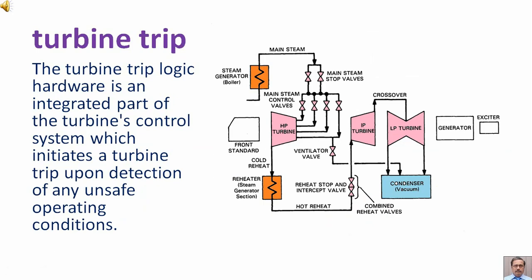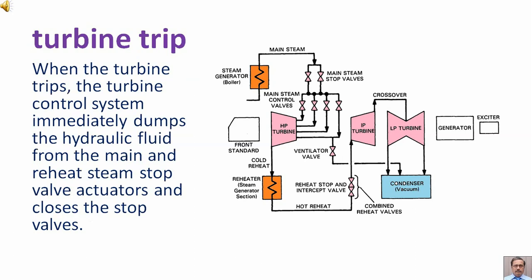Turbine trip. The turbine trip logic hardware is an integrated part of the turbine's control system, which initiates a turbine trip upon detection of any unsafe operating conditions. When the turbine trips, the turbine control system immediately dumps the hydraulic fluid from the main and reheat stop valve actuators and closes the stop valves. Here we have the main steam stop valves and here we have the reheat valves.